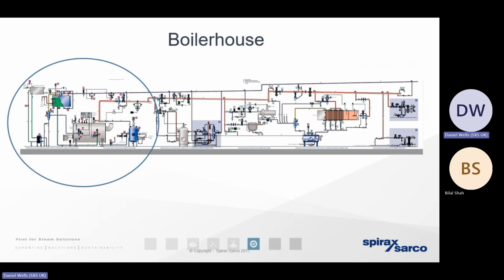So I'm going to skip very, very quickly now through very basic steam generation. So we're going to be installing those steam boilers. It can be anywhere between 1 and 6 in number in those horizontal fire tube boilers. It's typically at the corner of our client's campus for logistical reasons. And that means we can then be distributing the steam, what could potentially be thousands of meters around site. So it's vitally important that we control the condition of the steam as accurately as we can, so we don't have too much of that wet steam condensing in the pipework, and so that we can keep control of those mechanical issues and those inefficiencies.